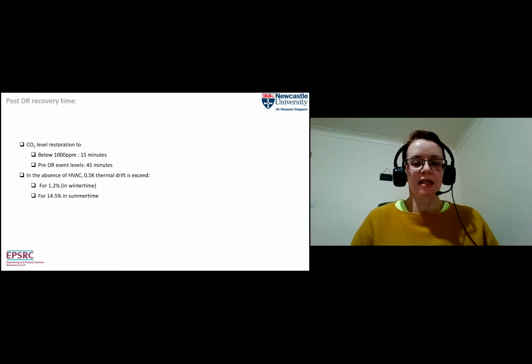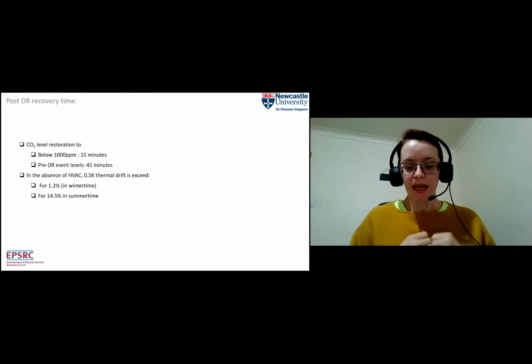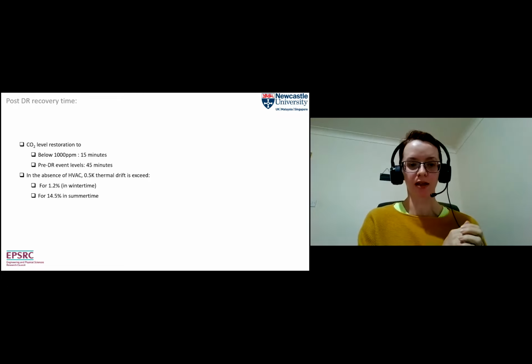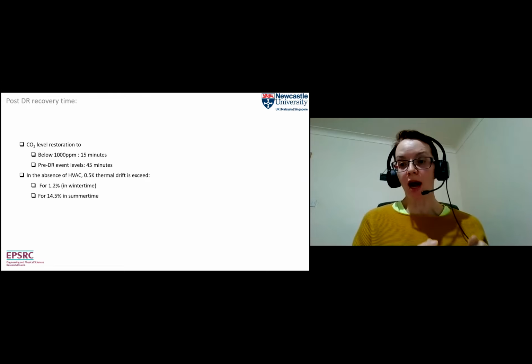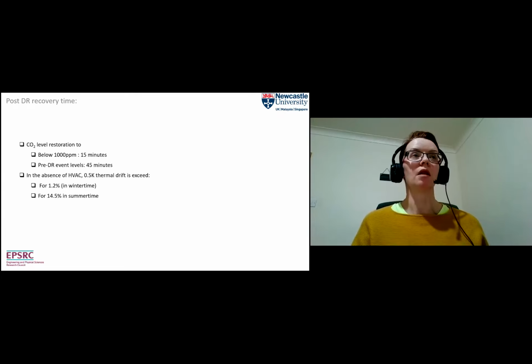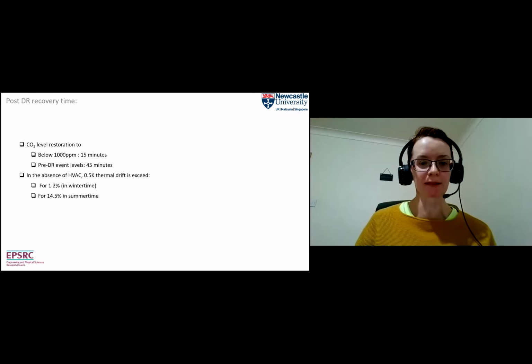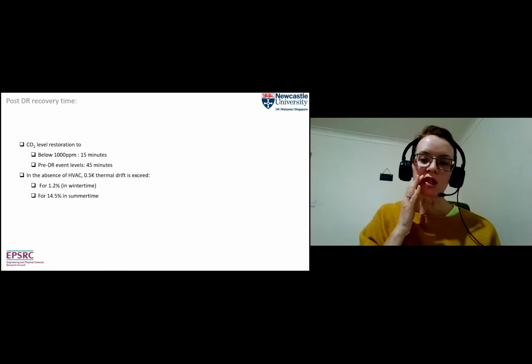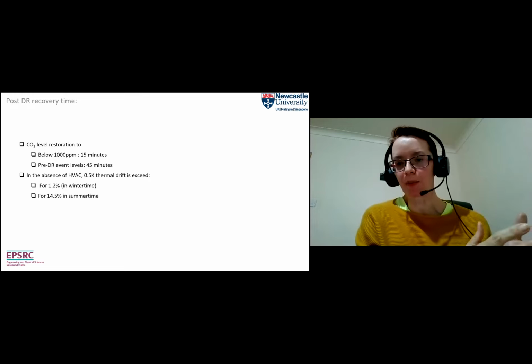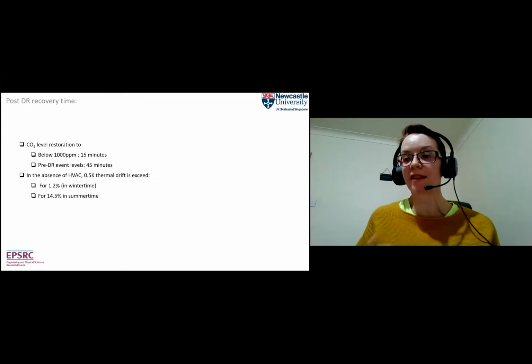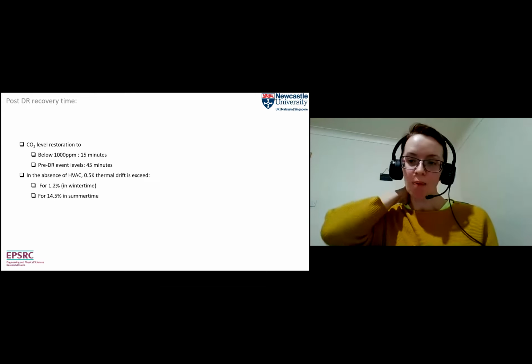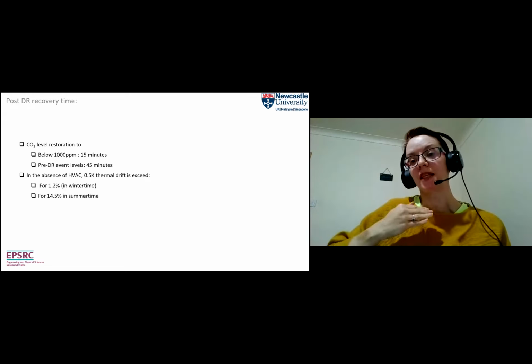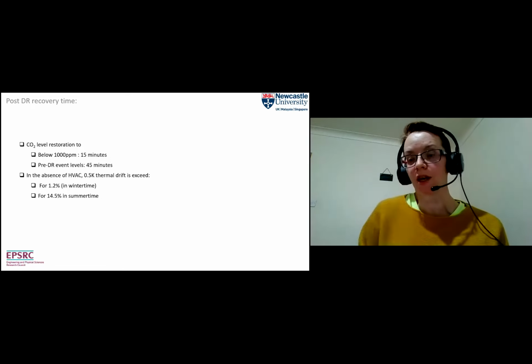But what we did find is that, in terms of controlling the building differently and helping the local electricity network at times of stress, we could do that for around half an hour for carbon dioxide, so ventilation, and for about 4 hours for the heat pumps without too much effect, I suppose, on people's experience of the building. We also looked at how quickly the building recovers and is ready to offer again after helping the network by being off for a bit. For the carbon dioxide levels, you do need to have the ventilation back on for a reasonable period before you can offer another half hour.